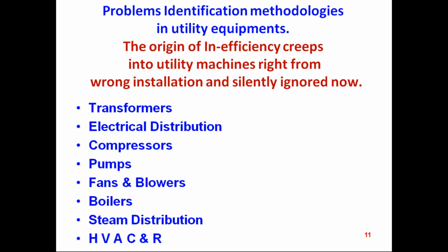a macro view of the given system, whether it is energy efficient. What does the nameplate say for the given blower or pump, whether it is efficient? Are we operating the pumps at 50% efficiency or at 80% efficiency? Are we operating the blowers at, see, these are all the ranges. The blower OEM says I am giving an efficiency of 80%, but ultimately the blower is operating at only 50%.